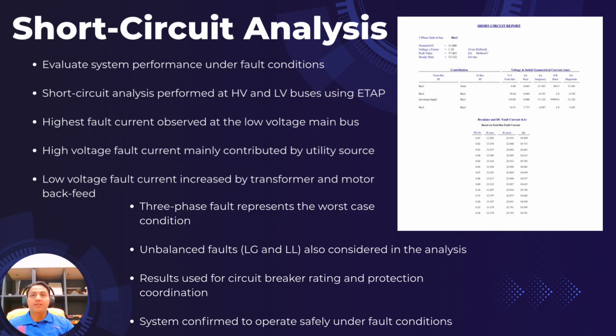We checked different types of faults, such as a three-phase fault and a line-to-ground fault. Although a three-phase fault produces a high current, the other fault types are still important for protection design. Overall, the short circuit results show the system is properly designed and the protection devices are suitable to operate safely during fault conditions.